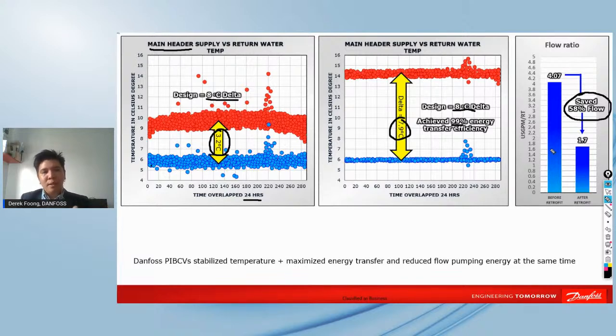Now, what is more important is not just the savings right here. Very importantly, if you look at the temperature behavior, it is oscillating and overlapping one another, right? There are a lot of oscillations in the system when a low return temperature is sent back to the chillers at times, and this is also considering the bypass is not stable. So unstable supply and return temperature reduces the lifespan of the chillers. So overall, we are talking about the OPEX, the life cycle of the system, not just energy. And we managed to reduce about 70% of the maximum deviation.